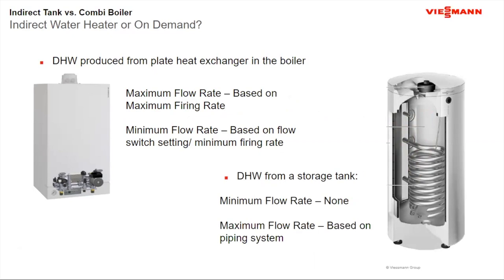Maximum flow rate really comes down to the piping connection coming in and out of the tank, what's the restriction there, and the associated piping as well. Over here, I may be limited to 4 gallons per minute with my combi boiler. I can have a 42-gallon tank and deliver 6 gallons a minute if necessary. So I can exceed what I think I need for short periods of time because of the volume of water that's available. The indirect water heater gives you flexibility in delivery.